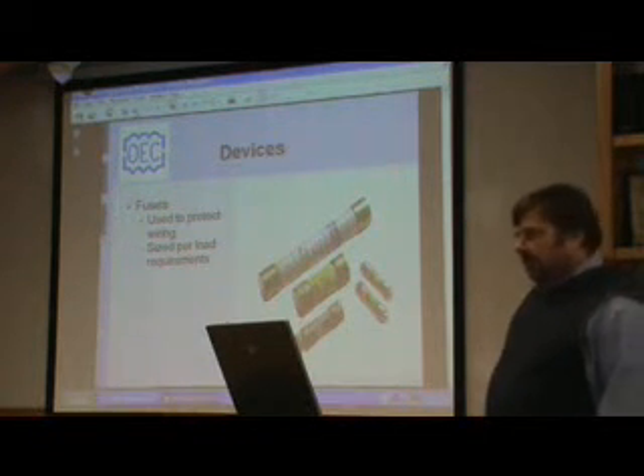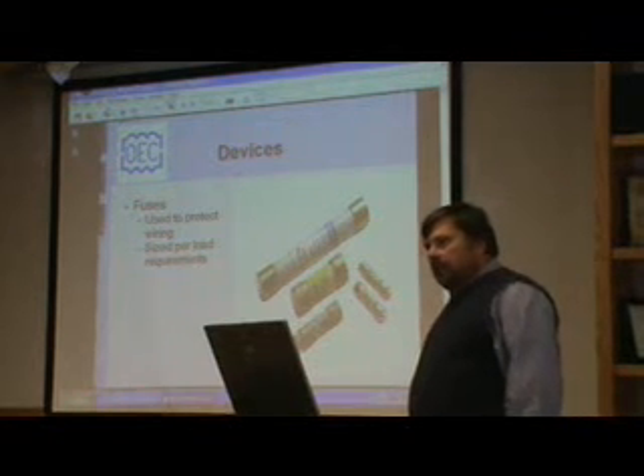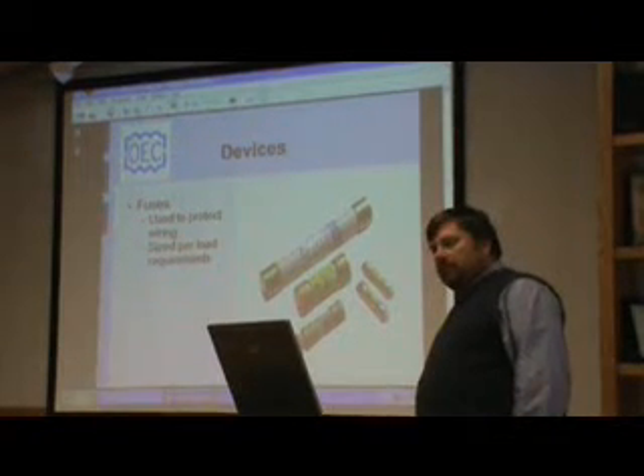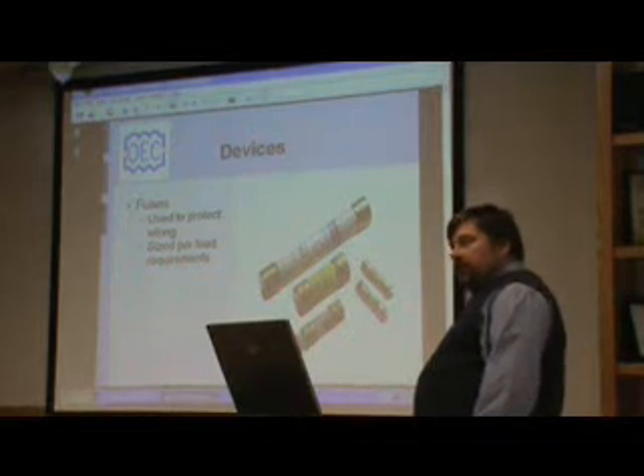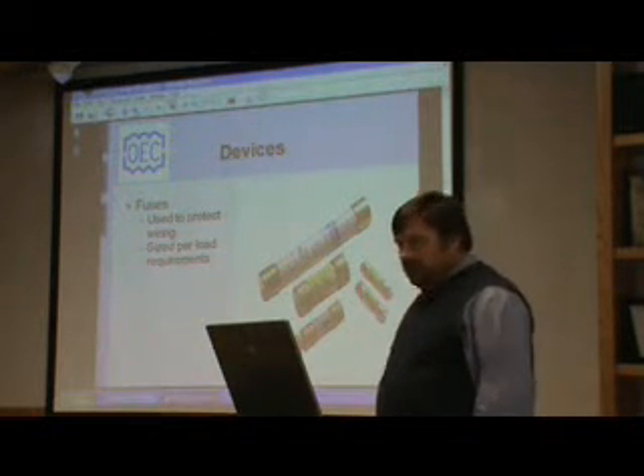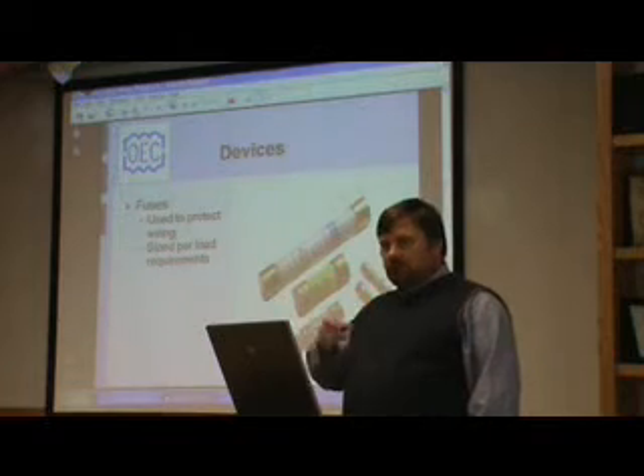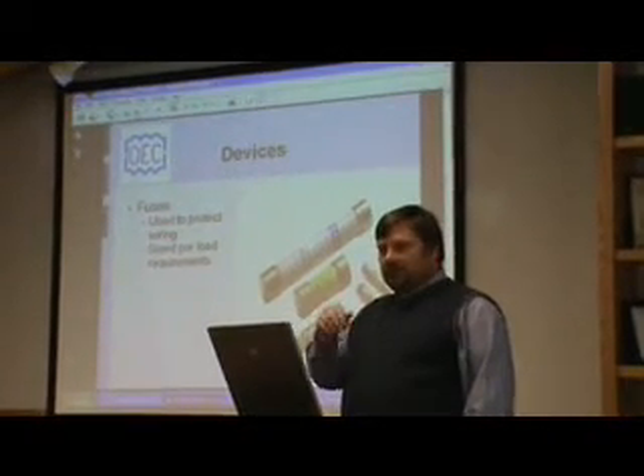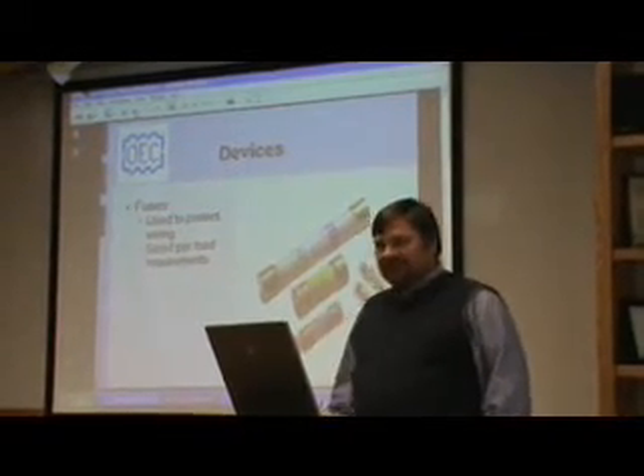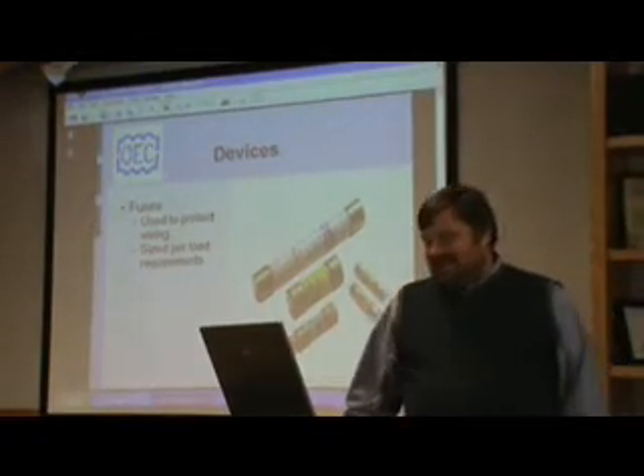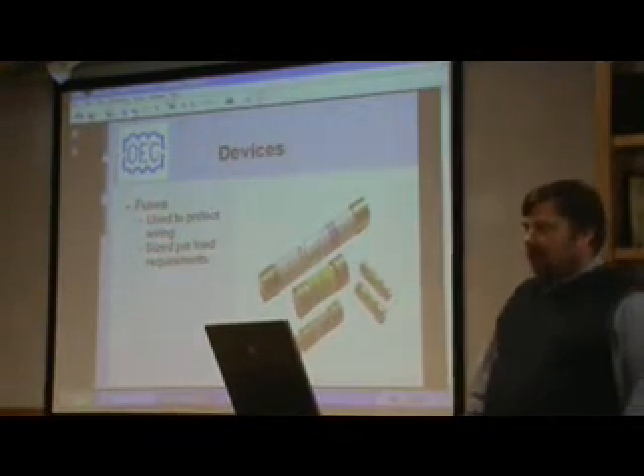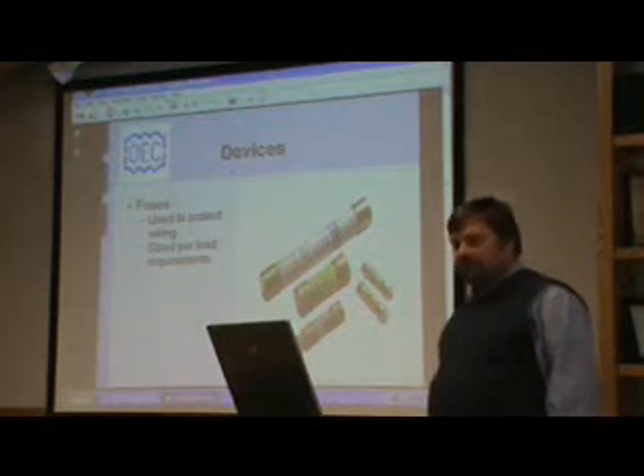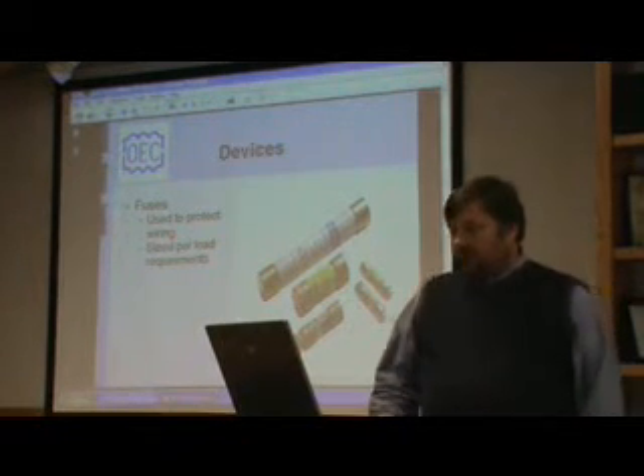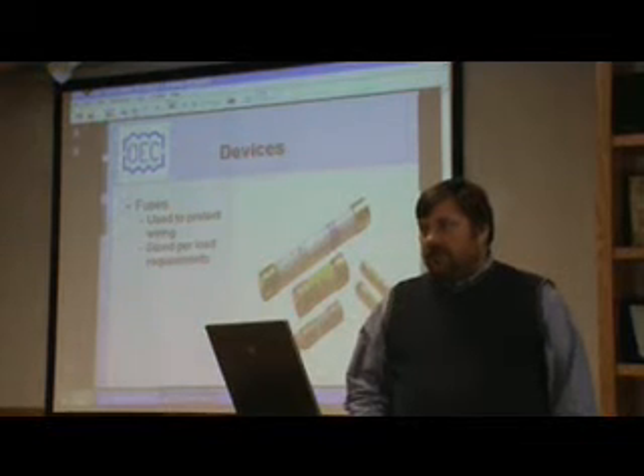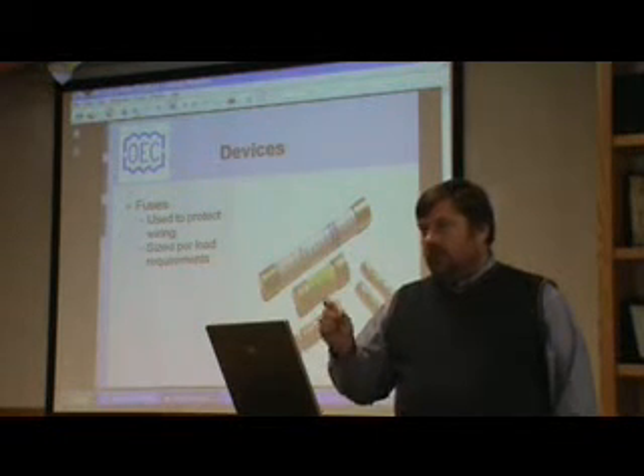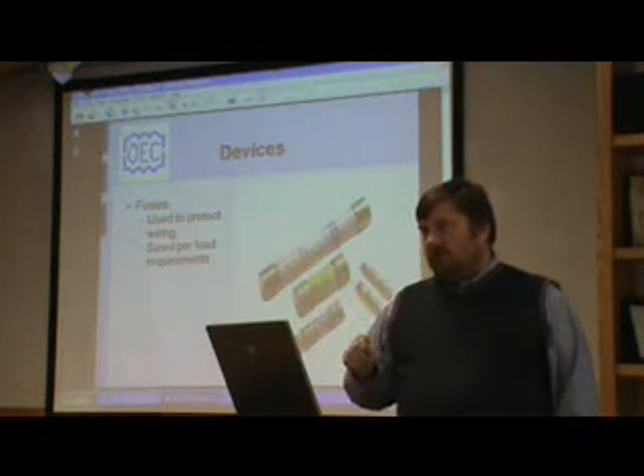So if you're using like a 16 gauge wire in your control circuit, you want to make sure that your fuses never go above 10 amp for a 16 gauge wire. My dad had this theory, he just kept putting in a larger size fuse until the fuse didn't blow, and then if that didn't work, you stuck a penny in and you were fine. So. But that's not the case. You need to make sure that the fuses are rated based on the wiring size that you have. And there again, they're sized per the load requirements.